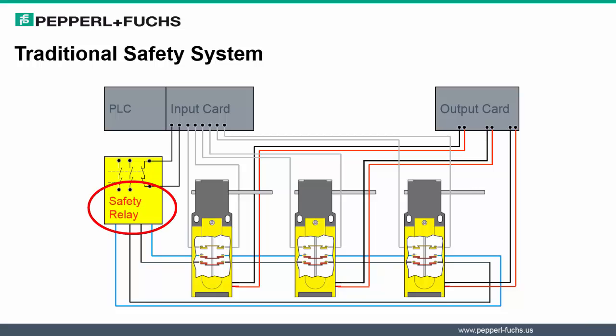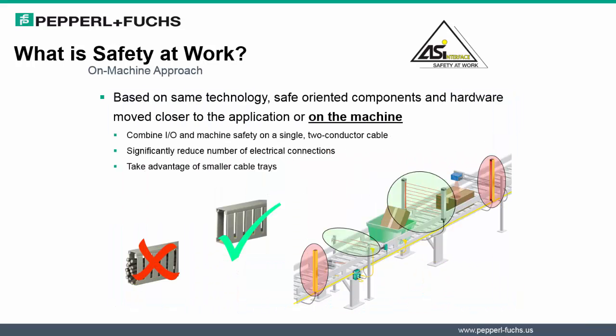The safety relay was an external yet essential component in conventional hardwire systems, which added further to additional wiring requirements. So, what is safety at work? Well, it's an on-machine approach. With AS Interface technology, safety-oriented components and hardware move closer to the application, or actually on the machine. Combining I/O and machine safety on a single two-wire cable simplifies designs and reduces installation time and cost. By reducing the number of electrical connections, cable trays can be significantly smaller and sizes of panels significantly reduced.